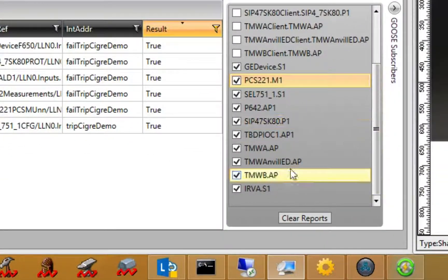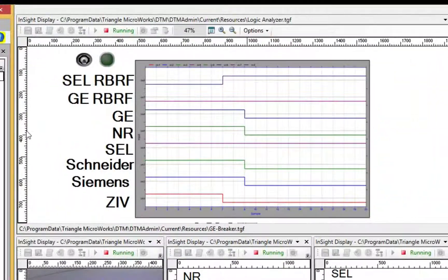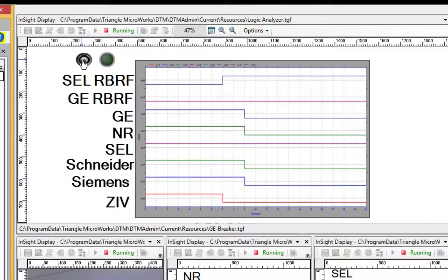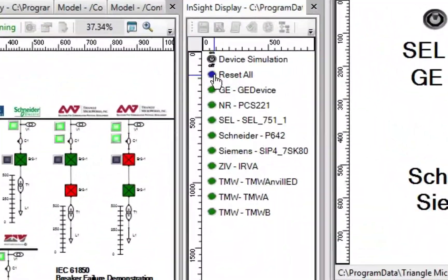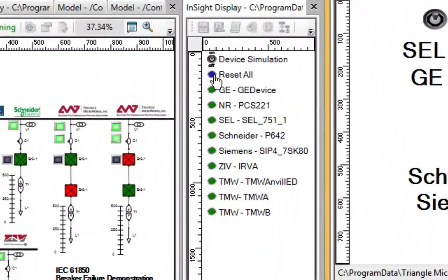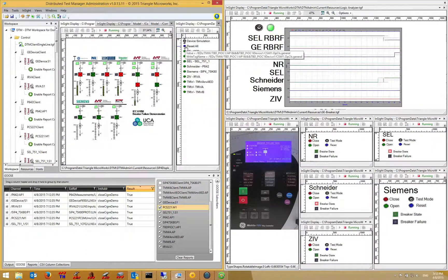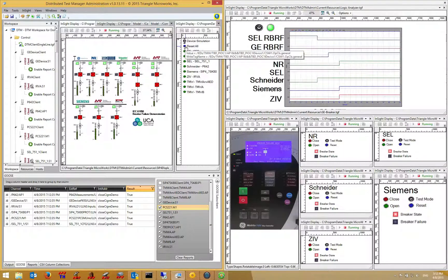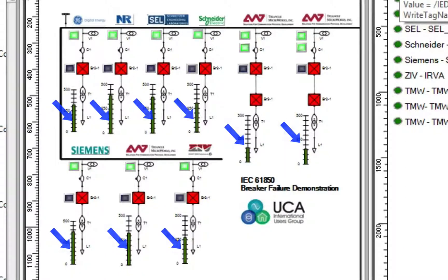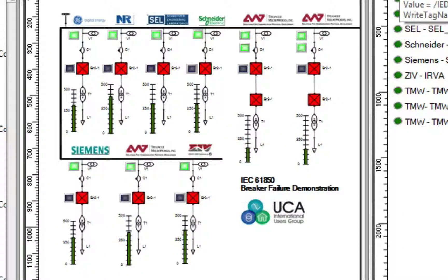Now let's clear the Goose report log again, re-enable the logic analyzer, and reset the breakers. As we do, we'll see each of the breakers reclose. Once again, we can see the current values being updated as they simulate the variation from a random load on a base value.